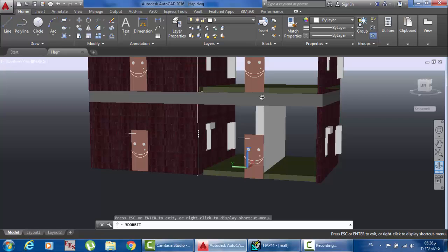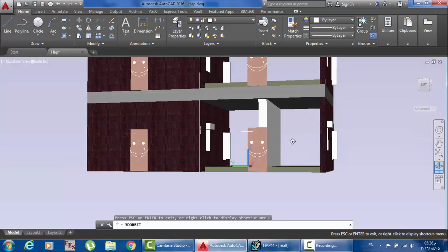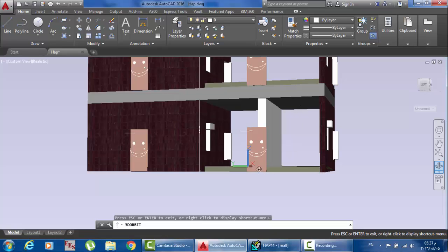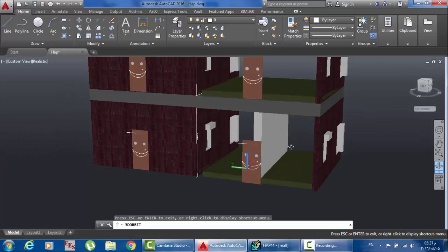This takes into consideration the safety factor, and actually it reduces the cost. So you have to take 50% of the areas of the internal walls. You may take half of the area of this wall and take only the heat transfer from the floor or the ceiling, one of them. So this will work in a good way.